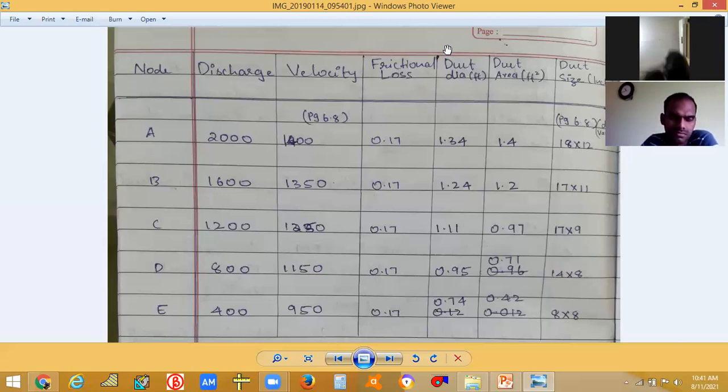So in this we are seeing the main duct, it is a supply duct. And the controlling factor you take as duct friction, because we are using the equal friction method. So what will be the velocity? This is the velocity in ducts. We are choosing private offices, directors' rooms, libraries, this application, and we are seeing the supply main duct, right? So what will be the velocity that we will be choosing from here?